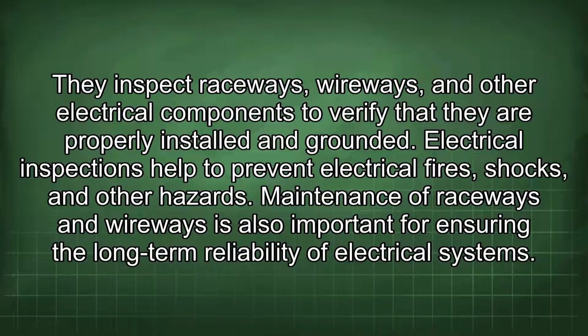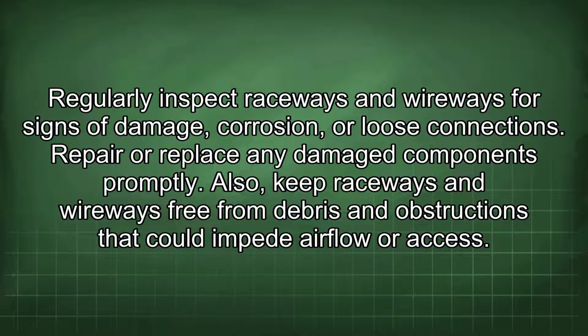Maintenance of raceways and wireways is also important for ensuring the long-term reliability of electrical systems. Regularly inspect raceways and wireways for signs of damage, corrosion, or loose connections. Repair or replace any damaged components promptly. Also, keep raceways and wireways free from debris and obstructions that could impede airflow or access.